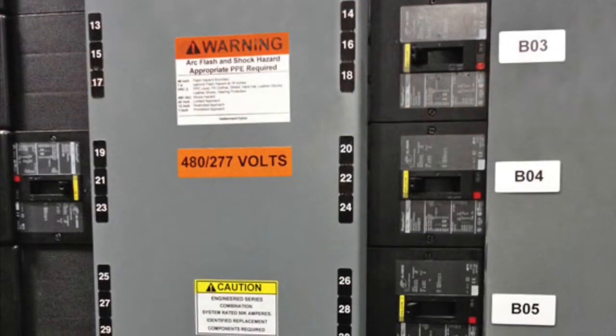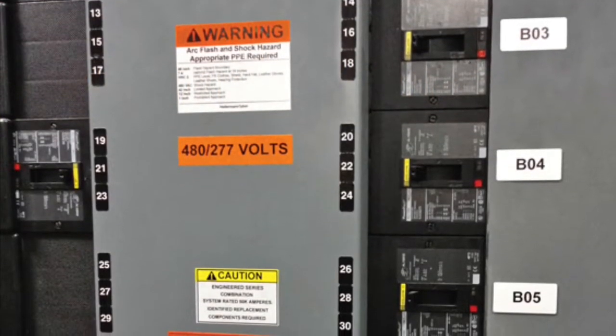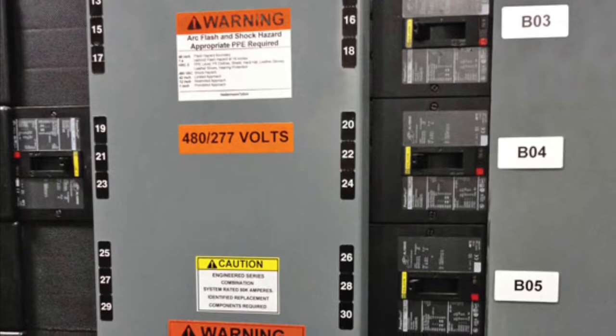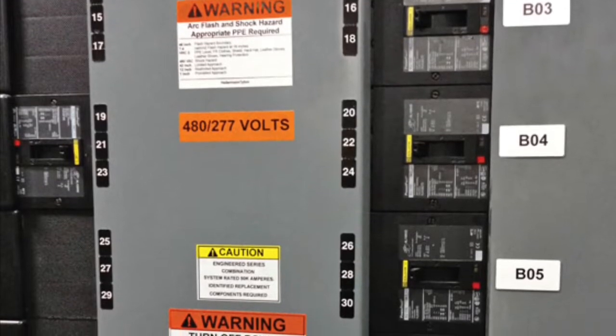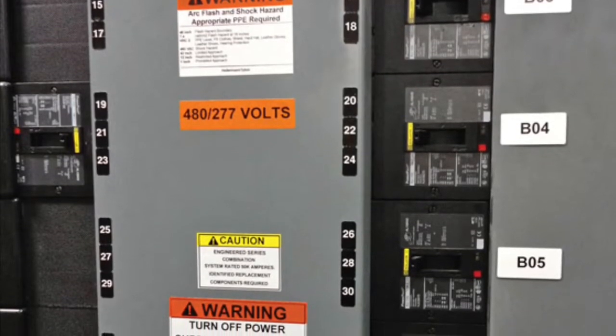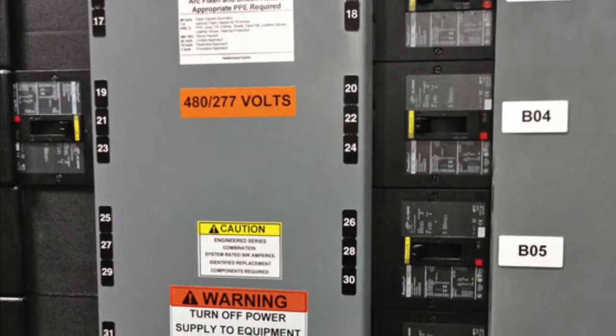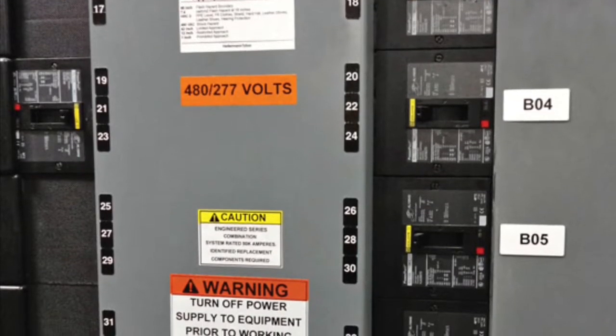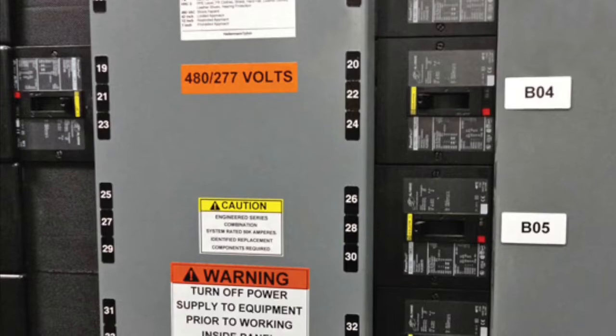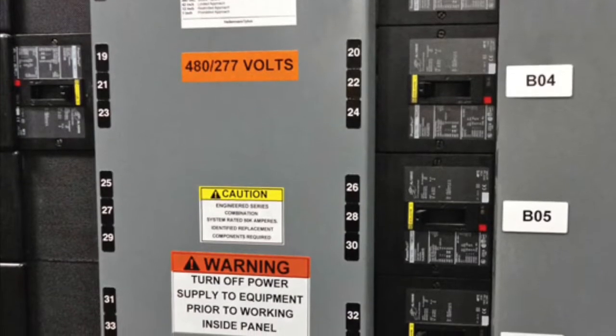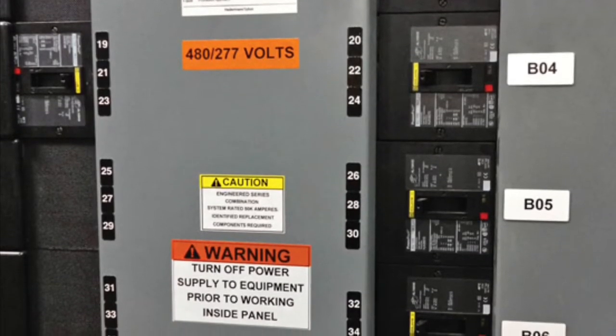The method of calculating and the data to support the information for the label shall be documented. The data shall be reviewed for accuracy at intervals not to exceed 5 years. Where the review of the data identifies a change that renders the label inaccurate, the label shall be updated. The owner of the electrical equipment shall be responsible for the documentation, installation, and maintenance of the marked label.